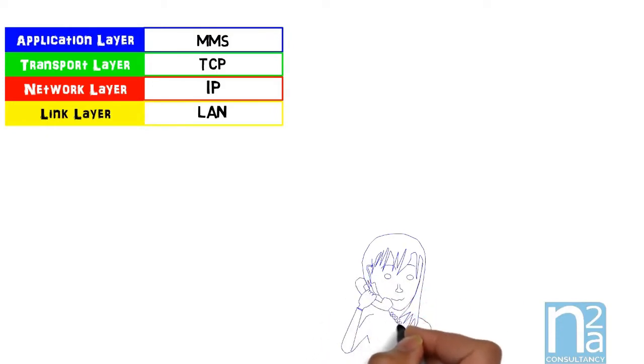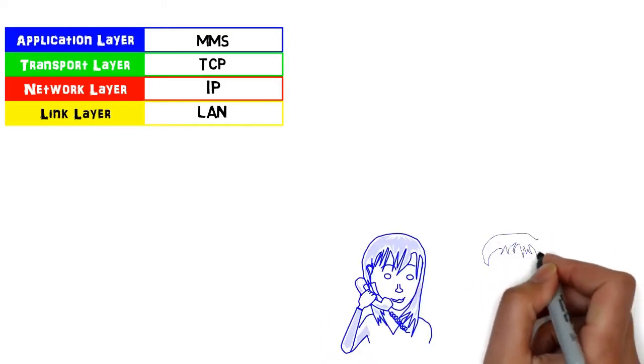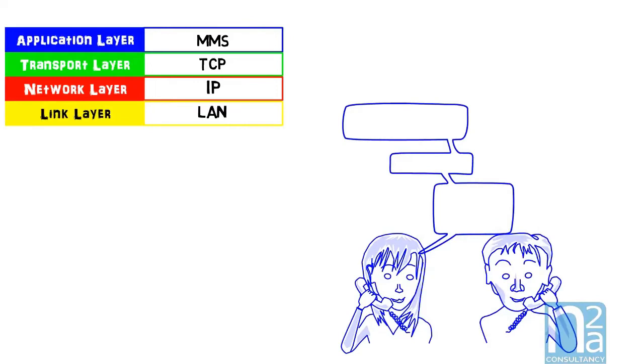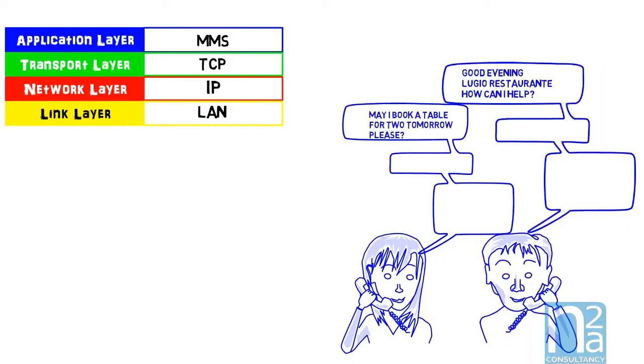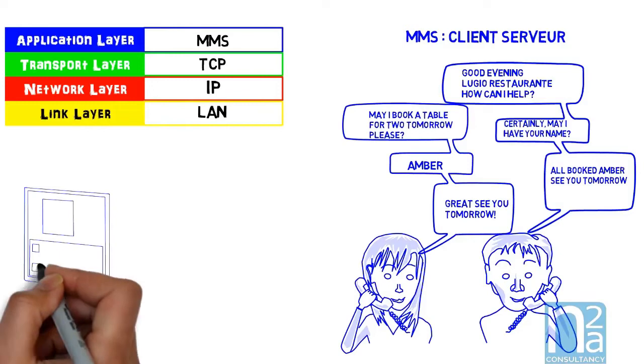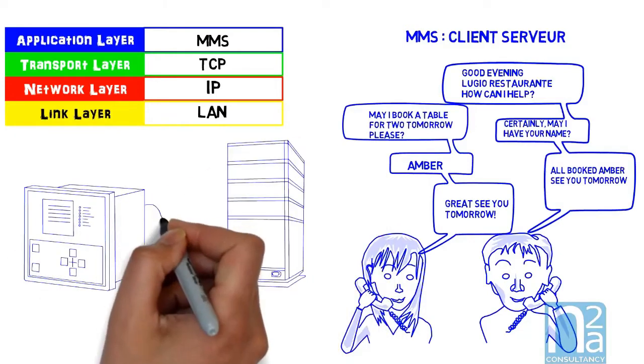First one, and the most used is MMS which stands for Manufacturing Message Specification. It is a standard internet application defined by ISO 9506. It is a client-server communication protocol, a private and secure conversation. The client sends a request to a server and the server sends back an answer. It is used for communication between the IEDs and the SCADA system to give status, make reporting or send control instructions.